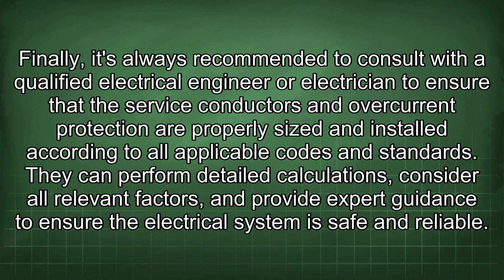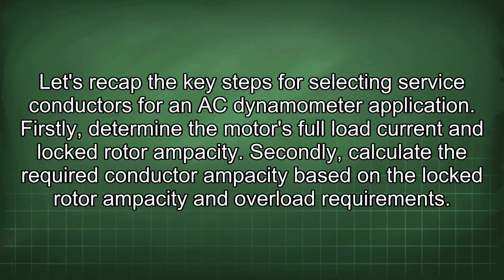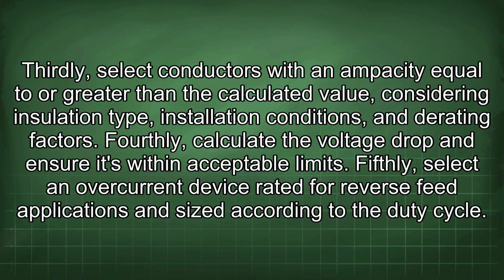They can perform detailed calculations, consider all relevant factors, and provide expert guidance to ensure the electrical system is safe and reliable. Let's recap the key steps for selecting service conductors for an AC dynamometer application. Firstly, determine the motor's full load current and locked rotor ampacity. Secondly, calculate the required conductor ampacity based on the locked rotor ampacity and overload requirements. Thirdly, select conductors with an ampacity equal to or greater than the calculated value, considering insulation type, installation conditions, and derating factors. Fourthly, calculate the voltage drop and ensure it's within acceptable limits.